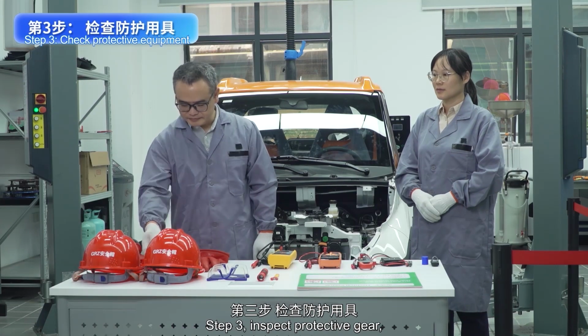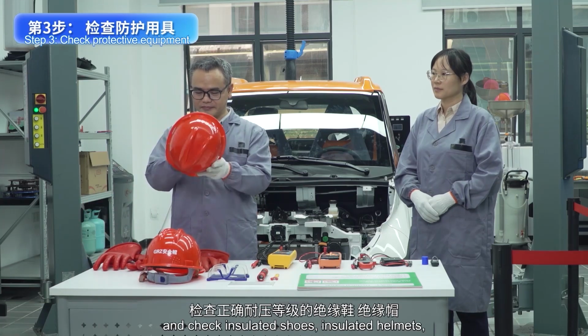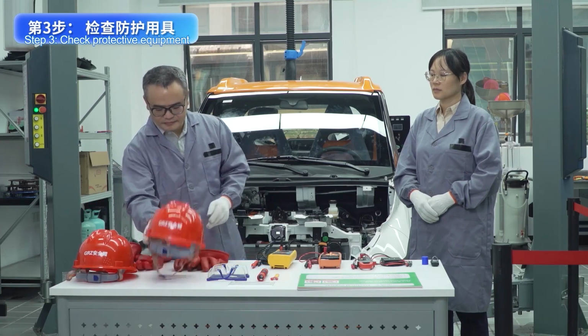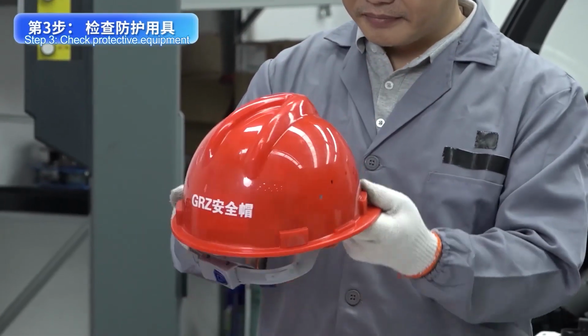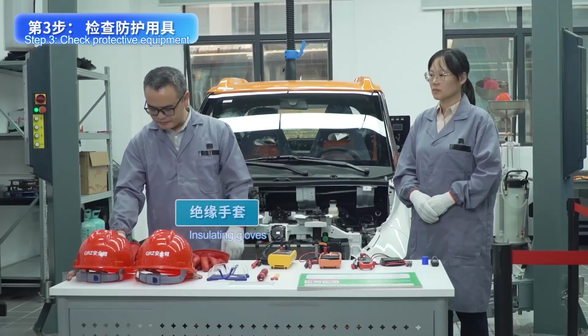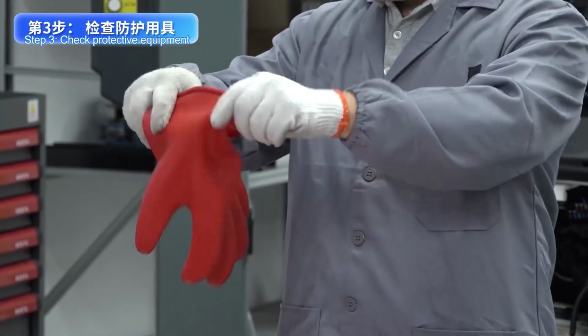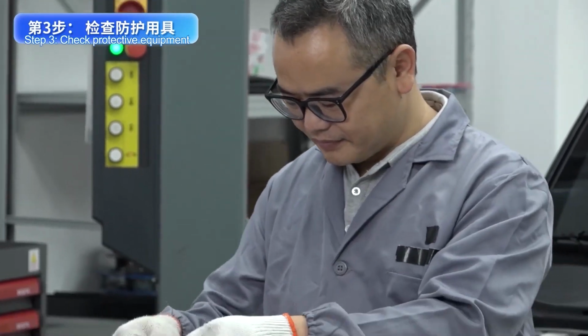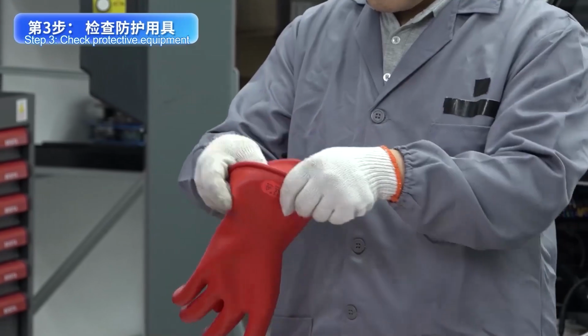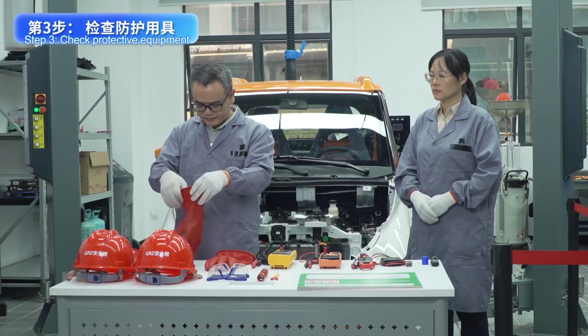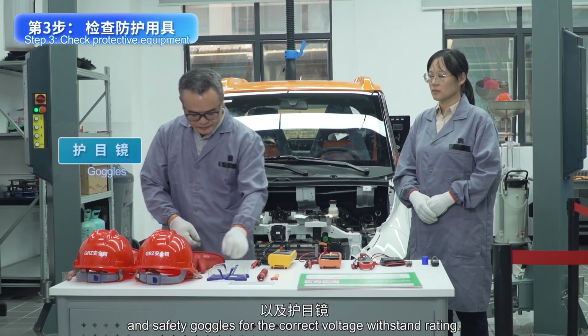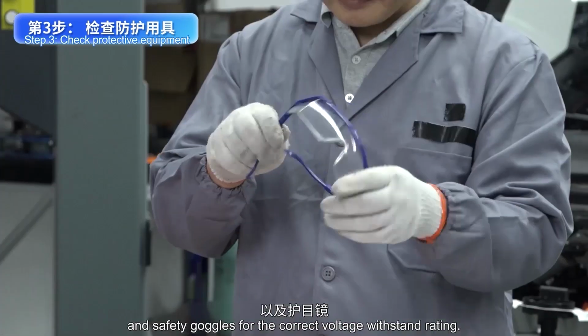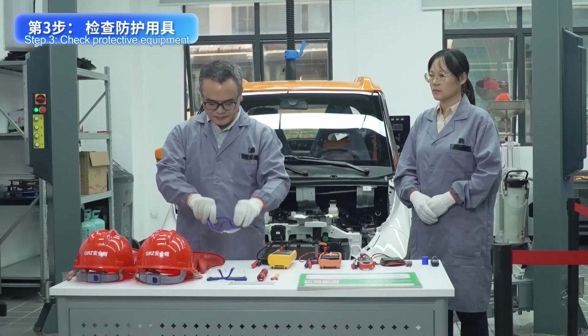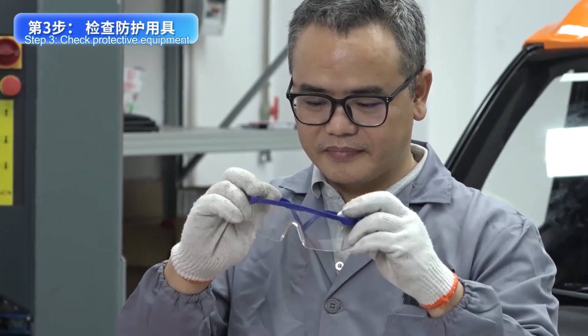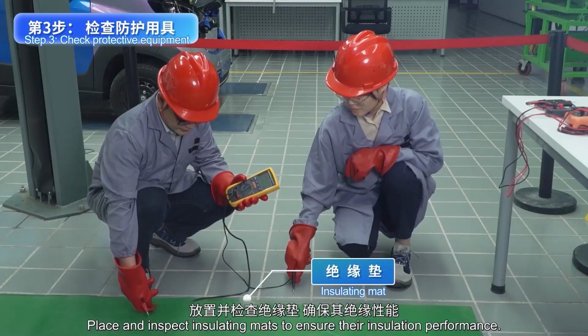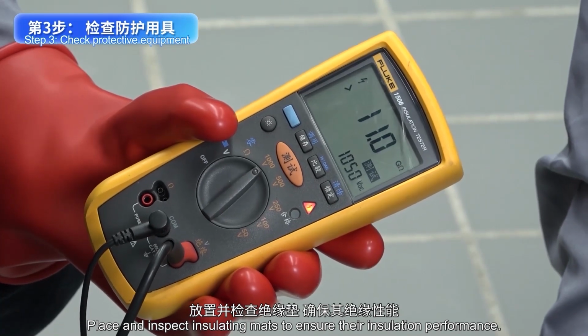Step 3. Inspect protective gear and check insulated shoes, insulated helmets, insulating gloves, and safety goggles for the correct voltage withstand rating. Place and inspect insulating mats to ensure their insulation performance.